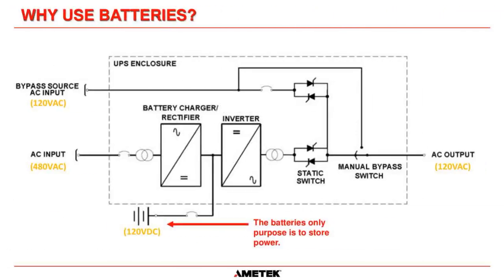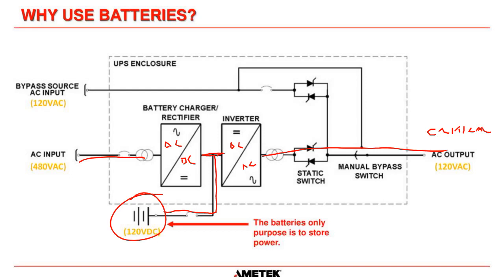And the same can be said for a UPS. This is a drawing from one of our AMETEK SCI manuals. We've got our AC input going in here. Then we convert AC to DC. And we've got our battery here. The charger is only there to supply power to keep the batteries charged, but the charger will supply power to the inverter, which converts the DC back into AC, and then that goes out to our critical loads out here. In truth, you can run our UPSs with the battery disconnect open, with no battery connected. It will run absolutely fine. It will supply your critical output loads. But if you have a power outage, then you're dead in the water. That's why the battery there is only to store power. So if you have an AC failure, you transfer to battery operation and you carry on supplying your critical load circuits.